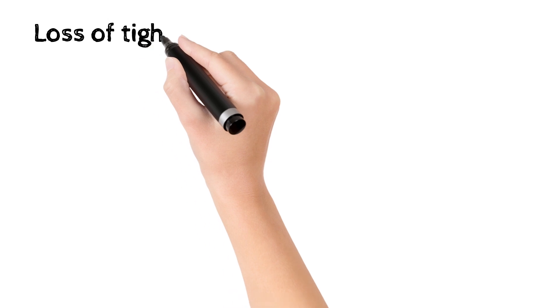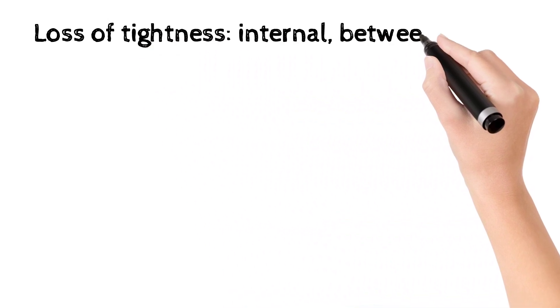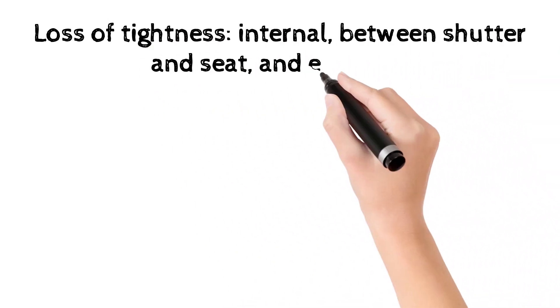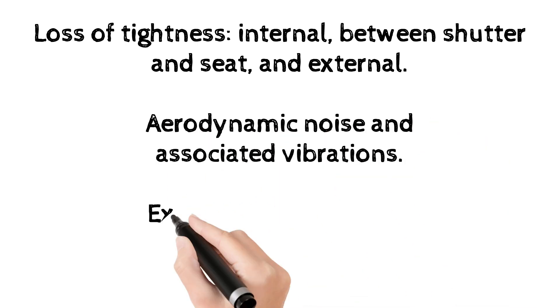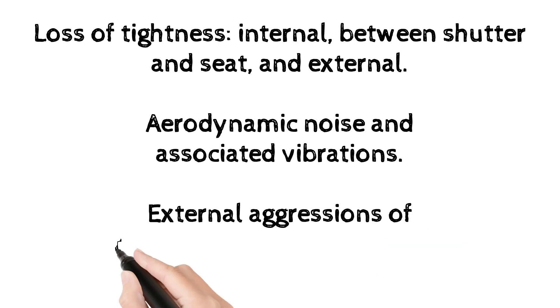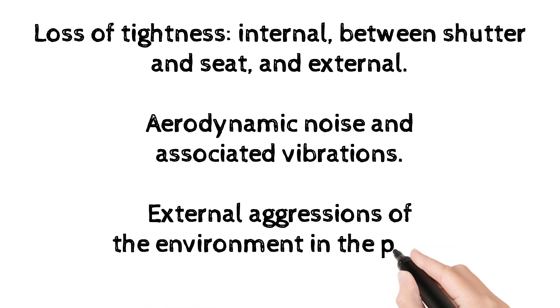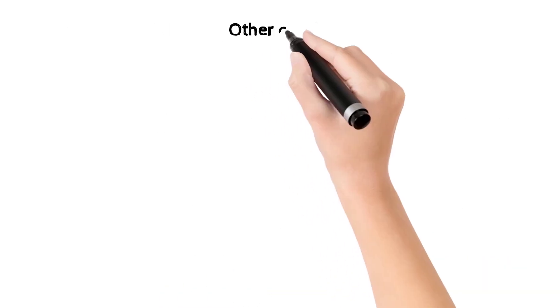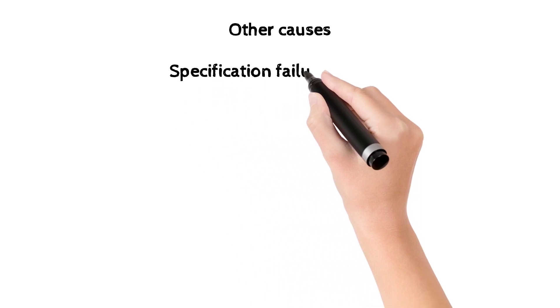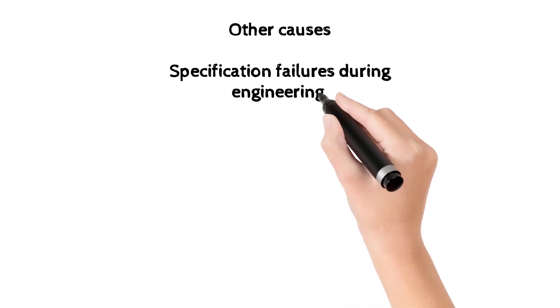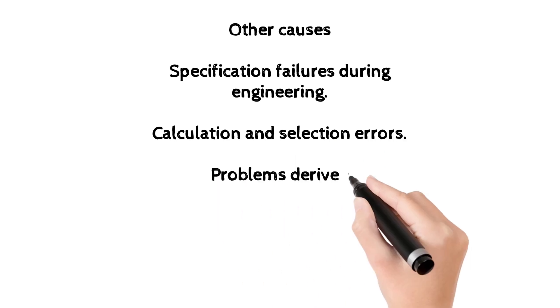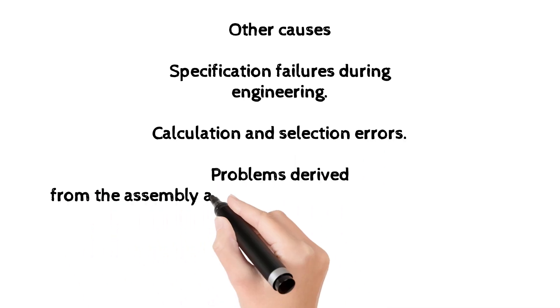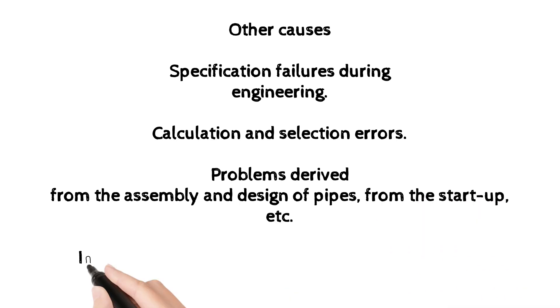Loss of tightness internal, between shutter and seat, and external. Aerodynamic noise and associated vibrations. External aggressions of the environment in the plant. Other causes: specification failures during engineering, calculation and selection errors, problems derived from the assembly and design of pipes from the start-up, etc. Inadequate maintenance in the first interventions.